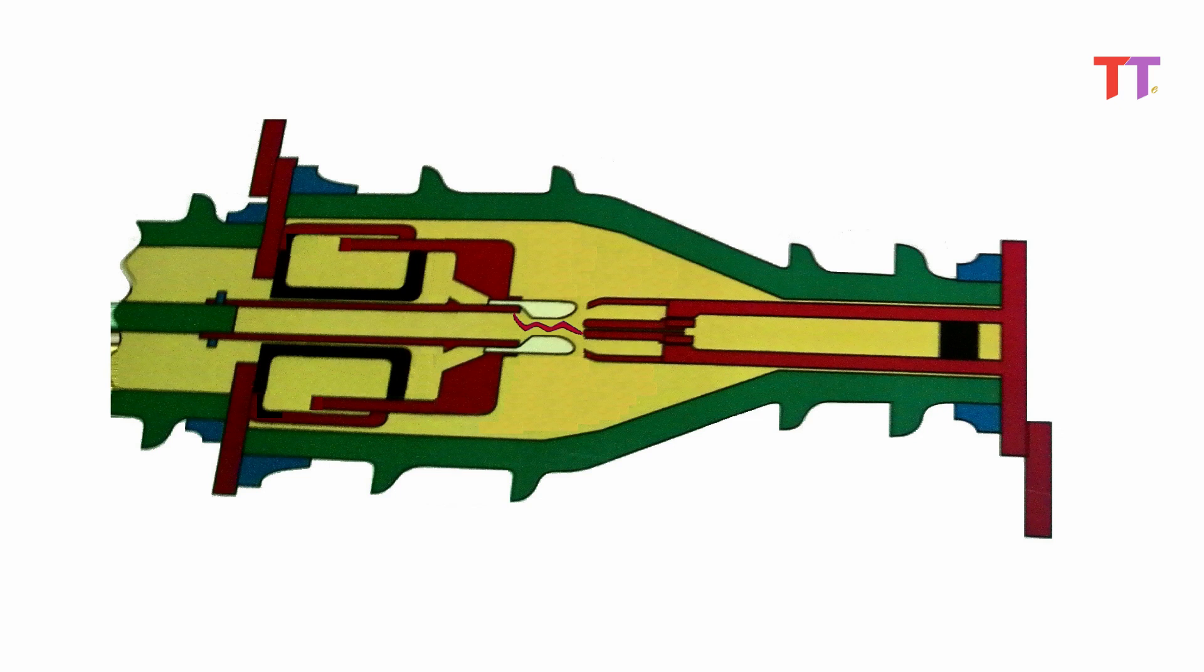Firstly, main contacts open, and then arc contacts open. Hence arc is produced between arc contacts. During this time SF6 accumulated between main contacts and pistons, gets compressed due to contact movement, is pushed into the arc region through nozzle.